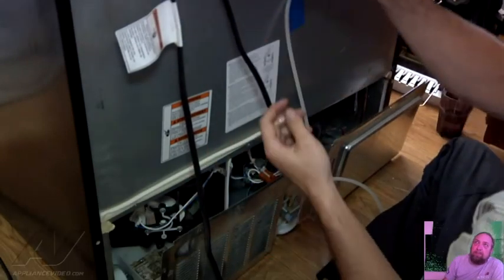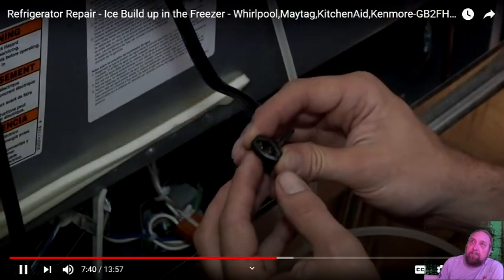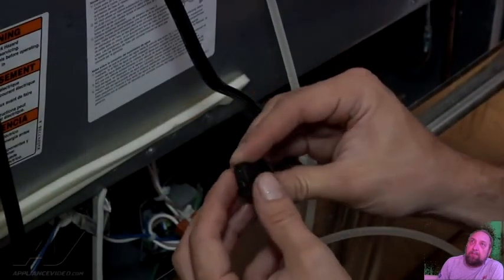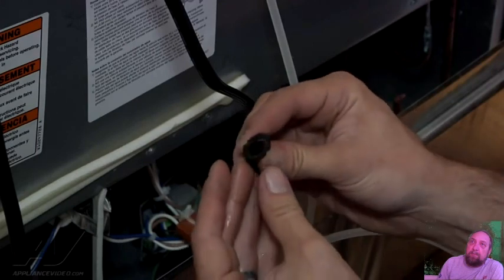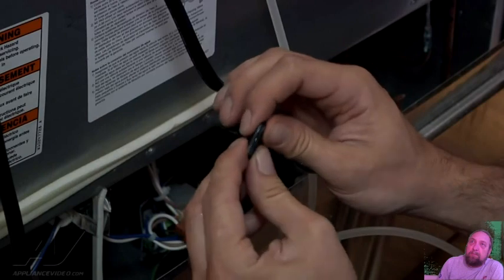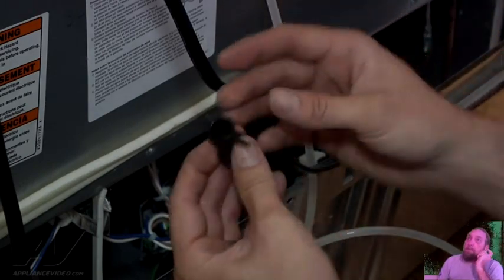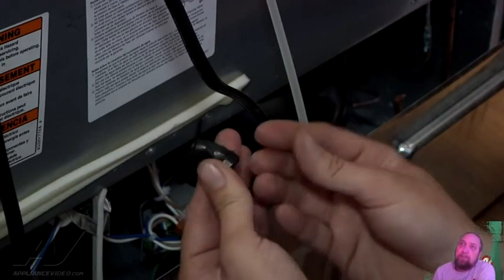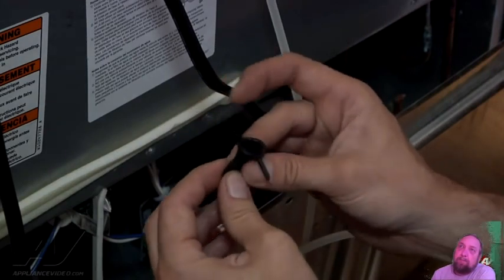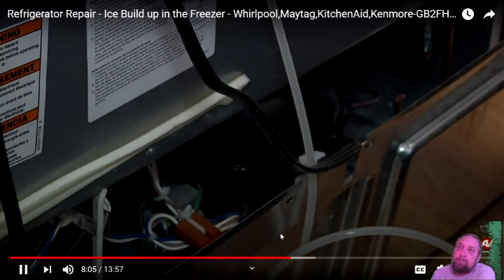What you've got is it's almost just gunked up and sticky. So if you look, the grommet's just dirty and really sticky. Like the heat of the compressor almost makes them just really kind of stick closed, and the water drains through here. The grommet just prevents warm air from coming up in and lets the water drain out. So we're going to put a new grommet on there because that one's obviously restricting the water flow.